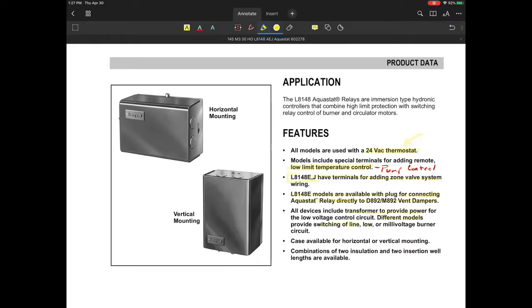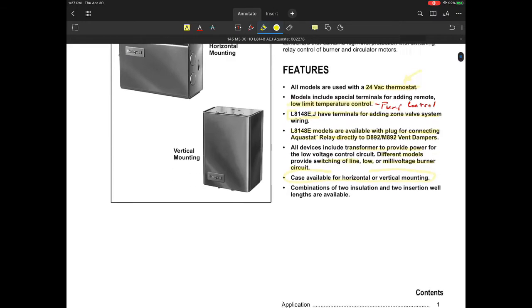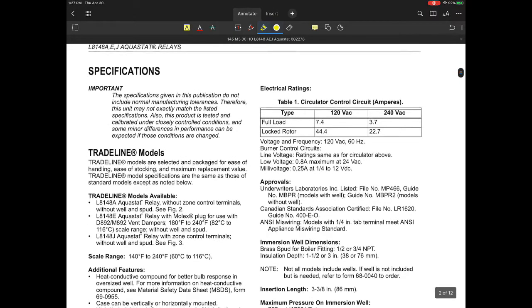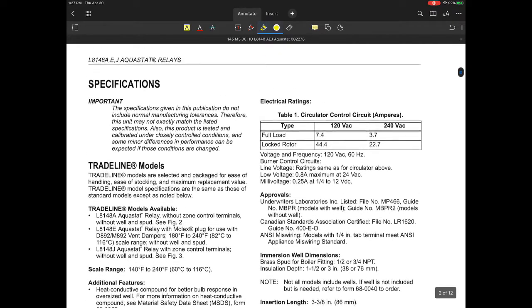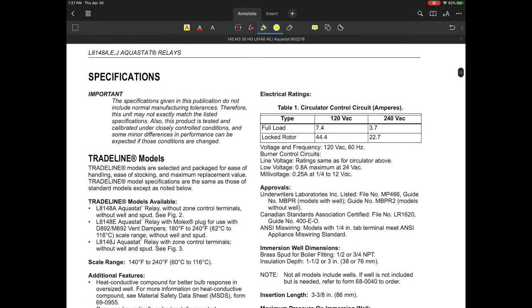They provide power to that low voltage circuit, and we'll talk about how they do that and what it does. This is the big thing right here: different models will provide switching of the line, the low, or even what they call millivoltage burner circuits. So you have to kind of know what you're looking at. And as I had mentioned earlier, they come in either a horizontal or a vertical mounting position. So we'll take a look further into that and proceed.